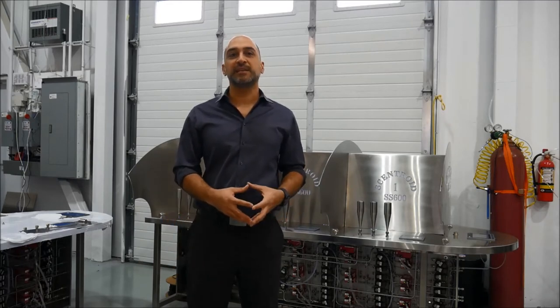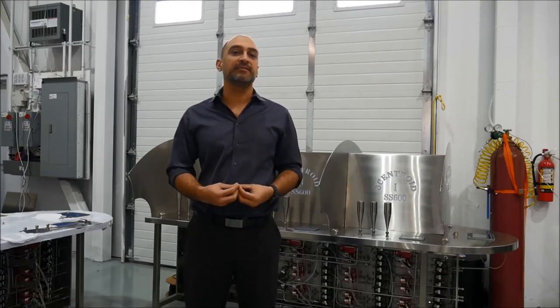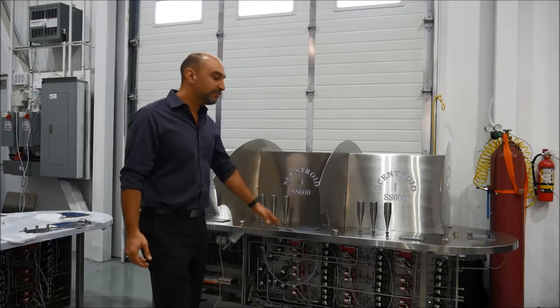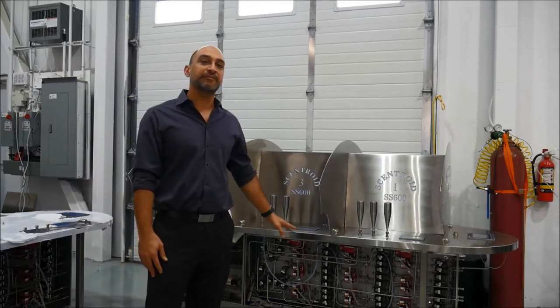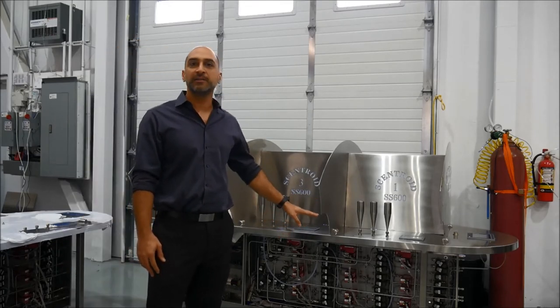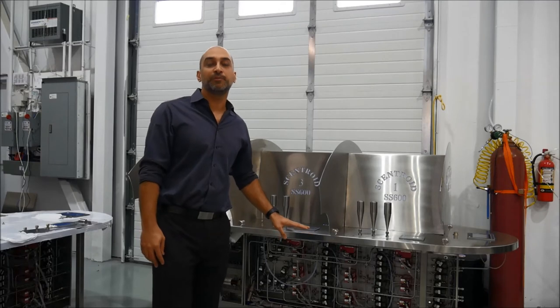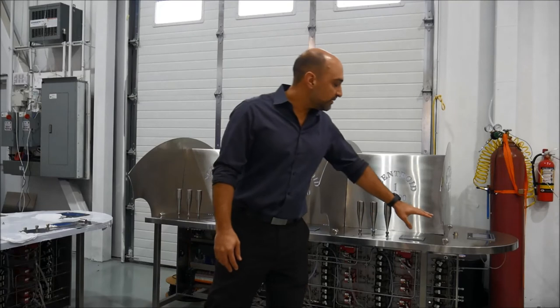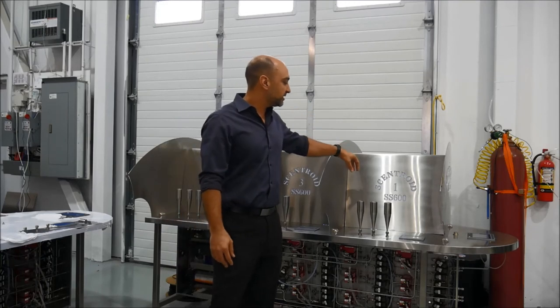The automated sequence allows you to detect how different odors are blended together, what the effect is in terms of concentration, and the overall hedonic tone of the perfume that they're making. If you look here, we left the doors open purposely so you can see. All the instrument is made with Teflon-coated stainless steel tubing. All the MFCs are medical-grade, achieving accuracy below 0.2% error. All the samples go on there — 9 different samples. You have 6 different stations and each station has 3 different ports.